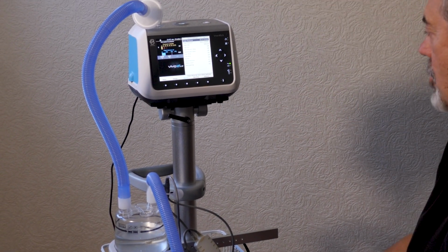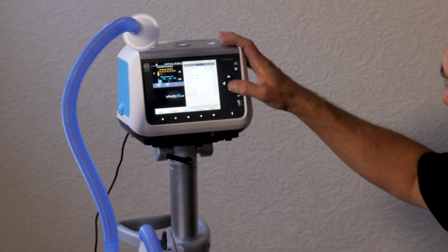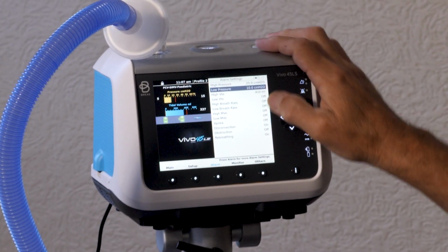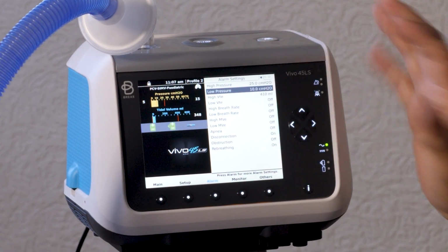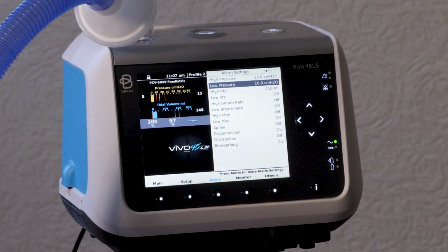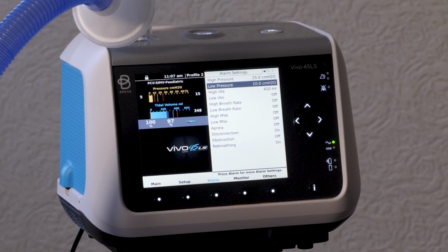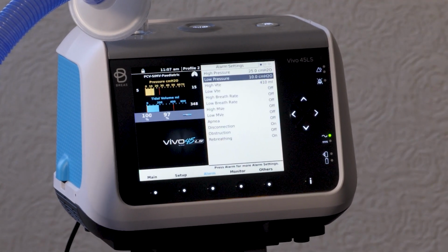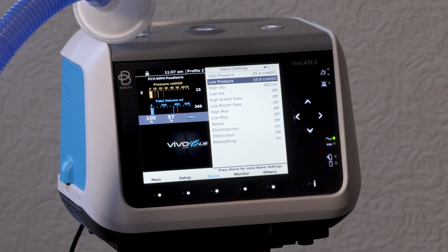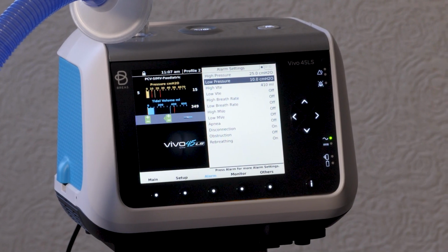We're going to go over some of the more important alarms. Again, low pressure, this is the next alarm on the list here. Low pressure basically means that you have a leak somewhere. And if you do have a leak somewhere, then the first thing you want to do is check the patient, make sure that the tracheostomy tube has not come out, that the ventilator circuit has not become detached from the tracheostomy tube.